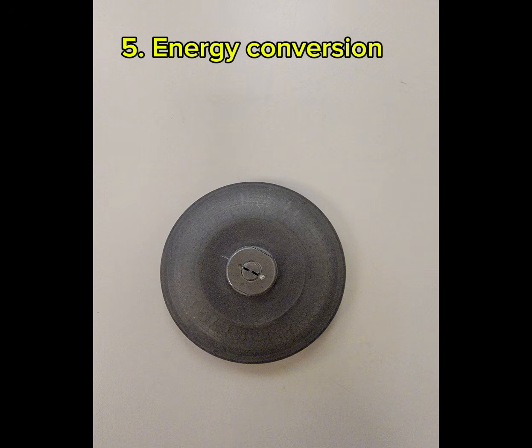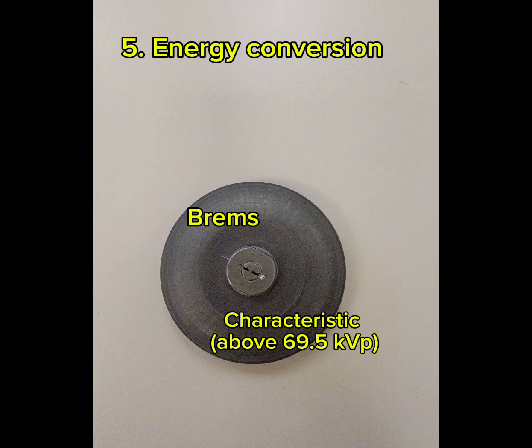Step 5 is energy conversion. So here we have just an anode pulled out, which is pretty cool because you can actually see the pitting of the anode in different areas where too much heat has been applied at the same spot without proper heat dissipation.